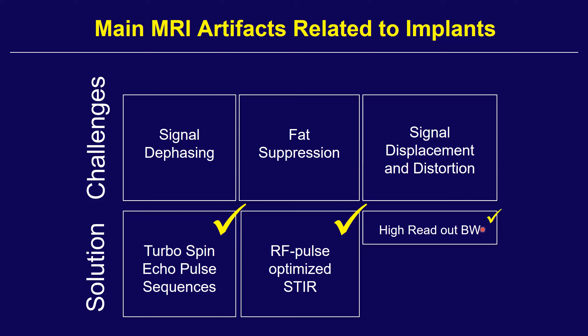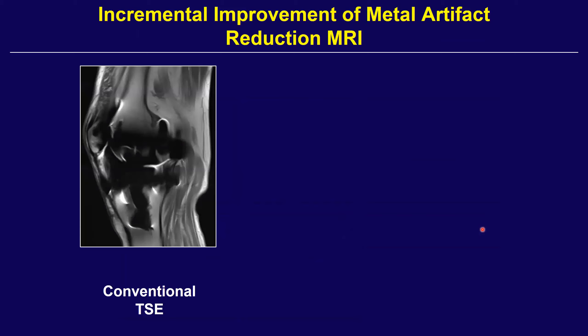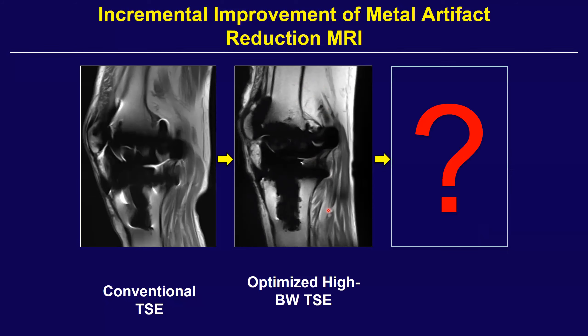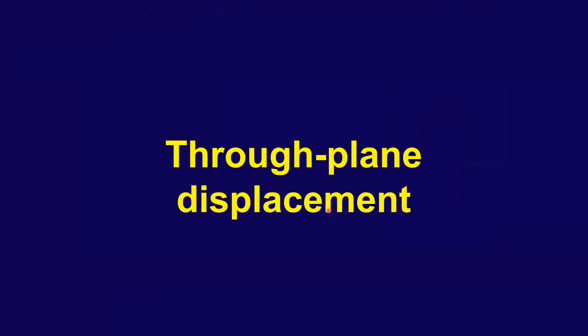This represents the evolution of metal suppression. With conventional FSE/TSE, we have lots of distortion and signal pileup. When we apply optimized high bandwidth TSE, we get significant improvement — less distortion, less signal displacement, and sharper images with better contrast. However, we are not fully there yet, because the through-plane displacement in the slice encoding direction has not been addressed. Sometimes you get high bandwidth images that look pretty good, but if you flip to a coronal scout with thick slices, you can see how bad the through-plane displacement is — almost a shepherd's crook in a distal femur tumor arthroplasty case.